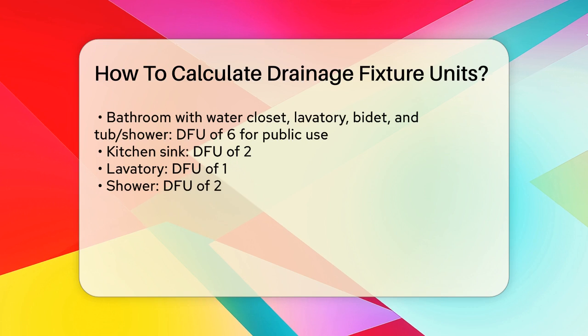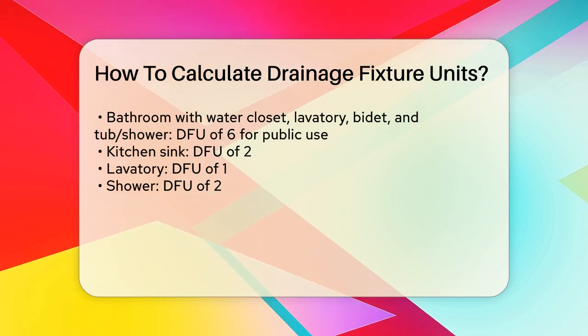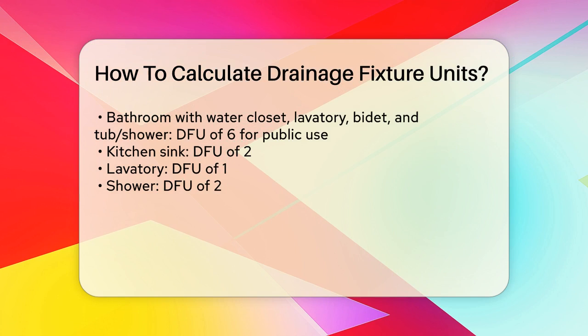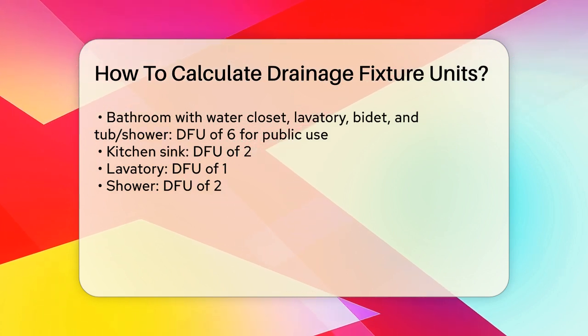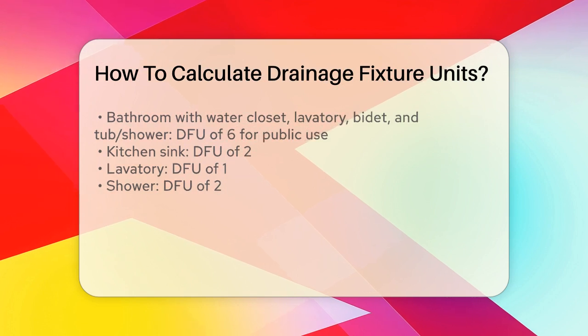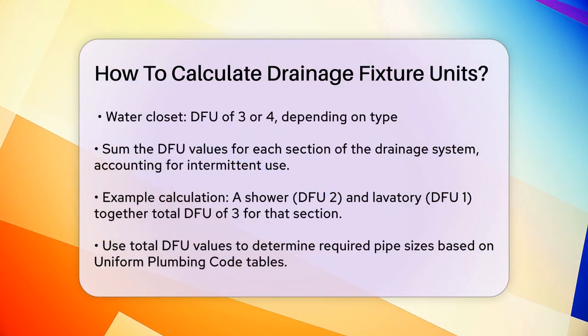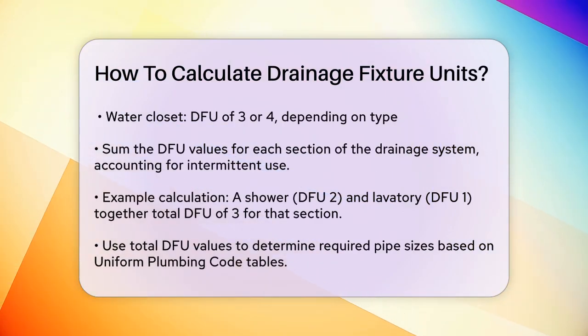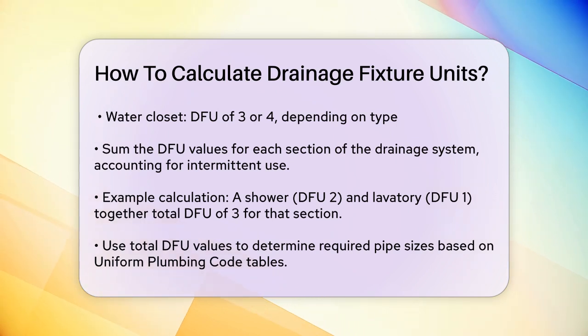Once you have the DFU values for each fixture, you need to sum them up for each section of the drainage system. This is because fixtures are never used all at the same time, so you need to account for intermittent use. For instance, if you have a pipe section that serves a shower with a DFU of two and a lavatory with a DFU of one, the total DFU for that section would be three.